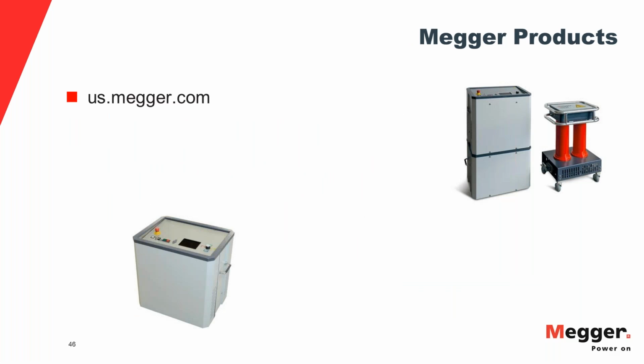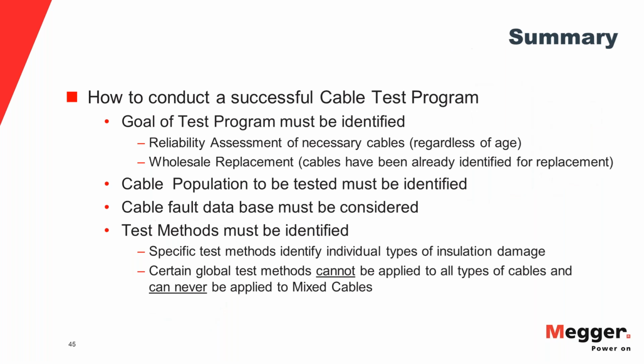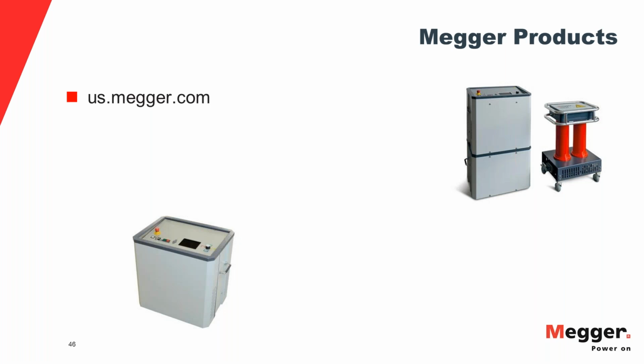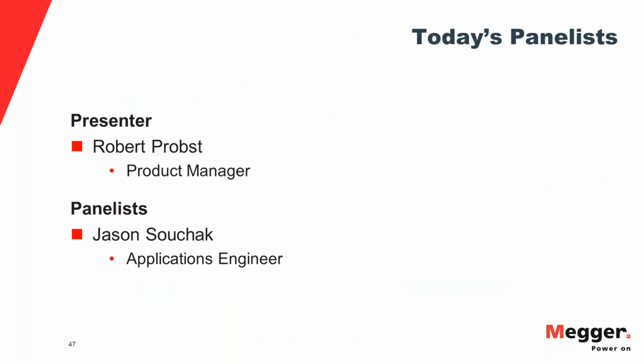Should I answer that or you answer that? I can take that one. Okay. So I think that what Robert was saying is that tan delta is a test that looks for aging conditions on the cable. And when you put new cables into the ground, it's impossible to have aging conditions on them. So when you do the test, you say, what am I looking for? I'm looking for something that can't possibly be there. I'm looking for aging on new cables.